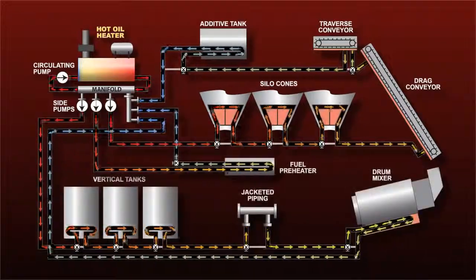After the oil transfers its heat to the components, it returns to the manifold. There, it's mixed with the hot oil flowing out of the heater coil and cooler oil returning from other circuits.